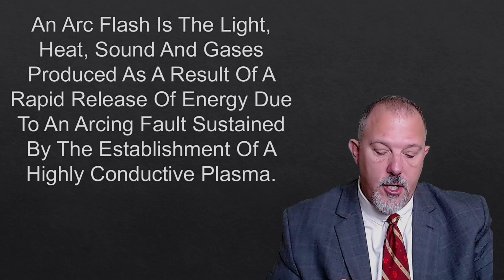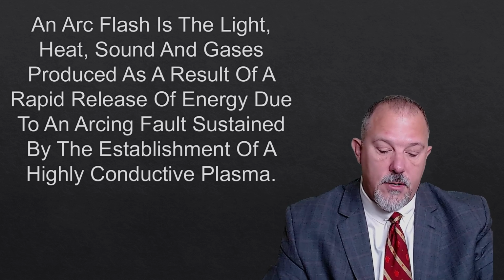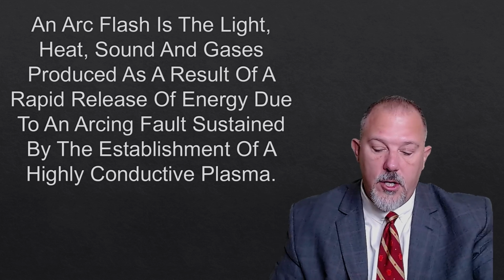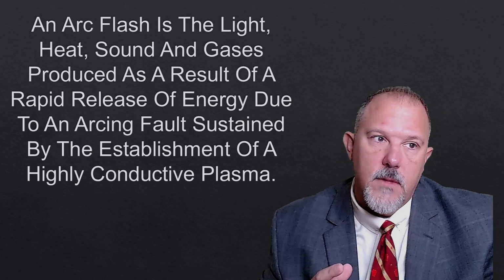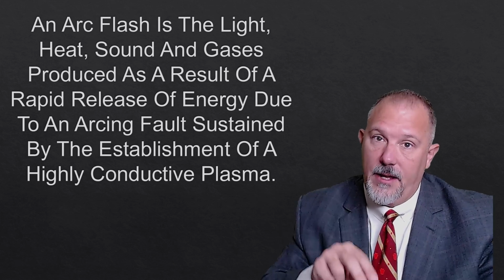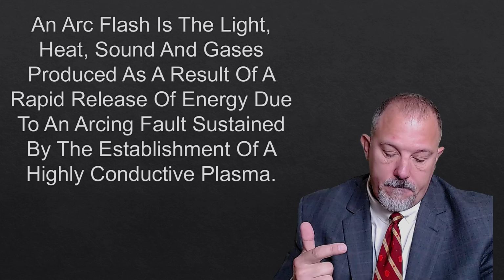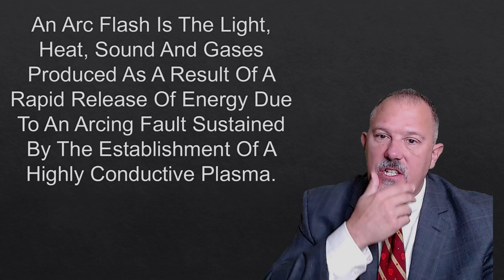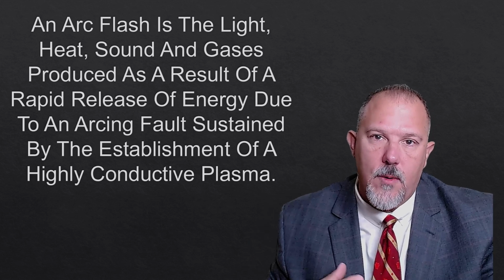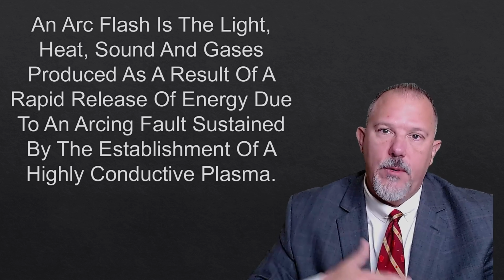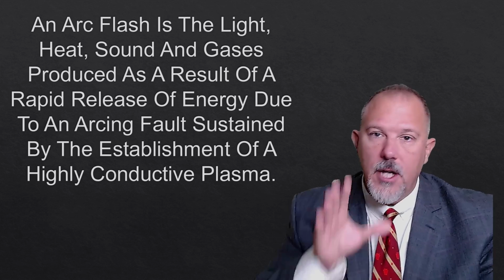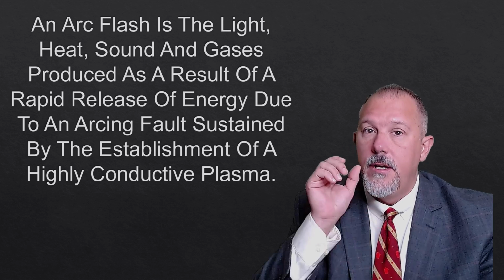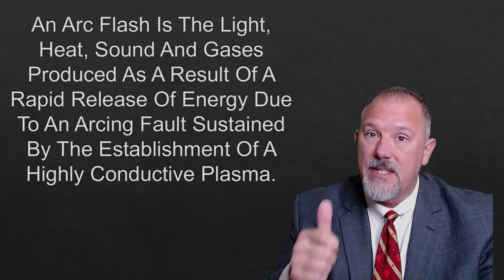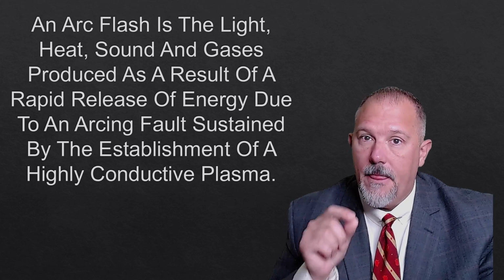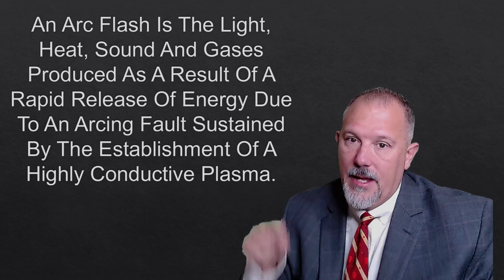And there's two informational notes. Informational note 1 says the likelihood of occurrence of an arc flash incident increases when energized electrical conductors or circuit parts are exposed. So we know that the arc flash event, the likelihood, and we're going to be talking about two key words today: likelihood and severity. And any time, and I'm going to ask you to do me a favor, when we look at the different code requirements, when you think about actions that we take in power distribution systems, when you're working on systems, look at your activity with an eye on likelihood and severity. What is the likelihood that something will happen, and what is the severity that something will happen? Two key words we're going to expand upon in this hour.